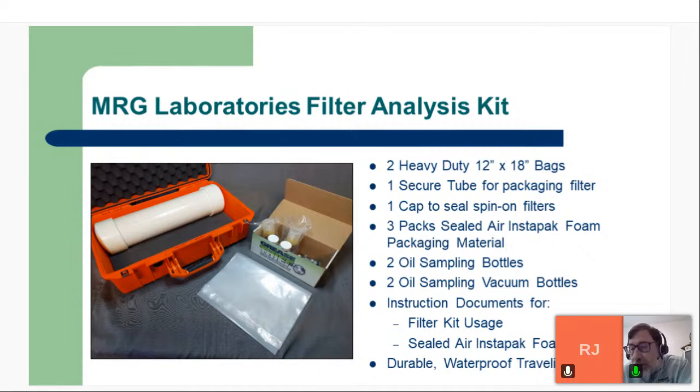So the kit will tell what the maximum size canister filter is that it could accommodate, and then the customer would have to identify if they have something different, and then we could customize to that. Yep. Whenever they would go to get that kit, we would make sure that the size is appropriate for what they have in house. And if the standard 4 inches would not work, yep, we could go larger or we could go smaller based on their needs.